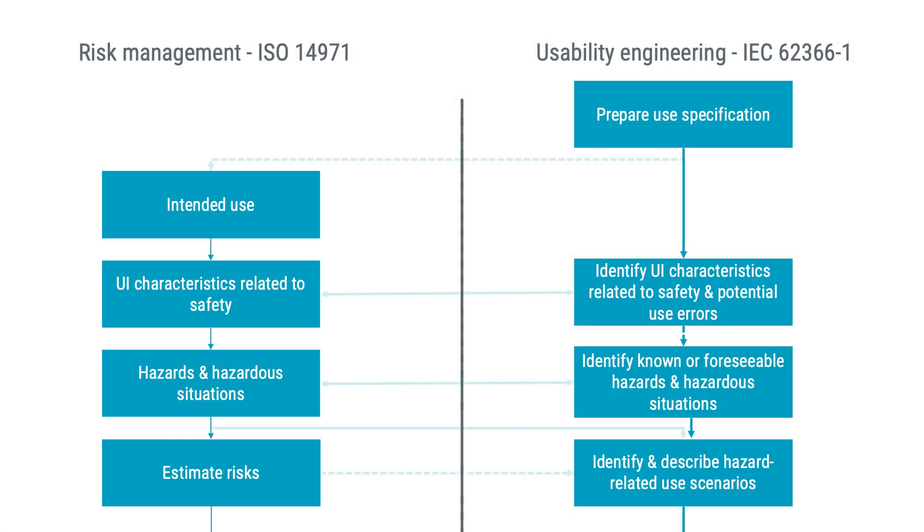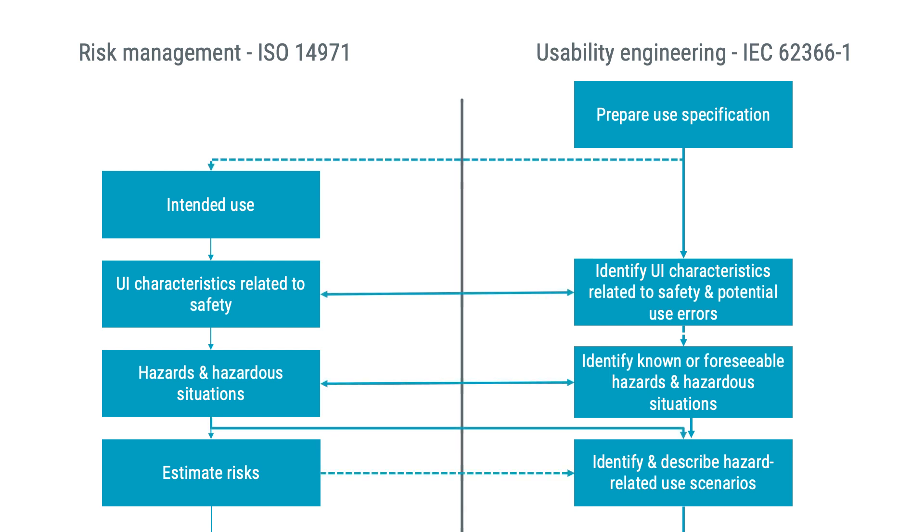If you take a look at the 62366-1 standard, there is even a flow chart showing how the usability engineering process is connected to the risk management process in one single picture. And as you can see here, usability engineering and risk management should be highly integrated. This is important to understand and remember when working with usability engineering. Your job as a usability engineer is to ensure that the device will be safe to use and has as low a risk as possible when it comes to the user interface.